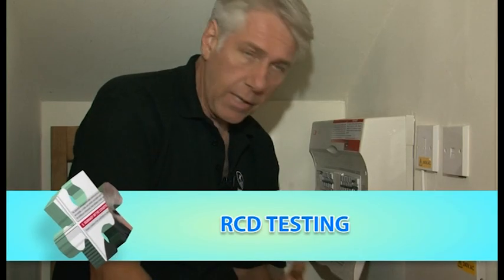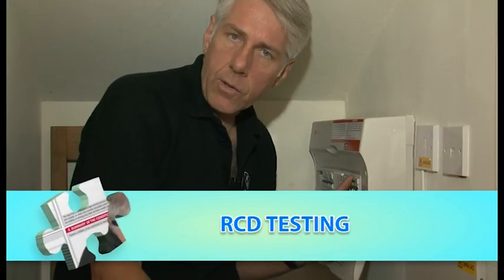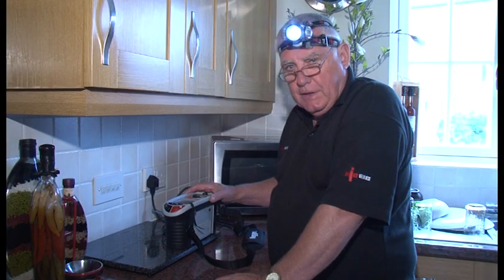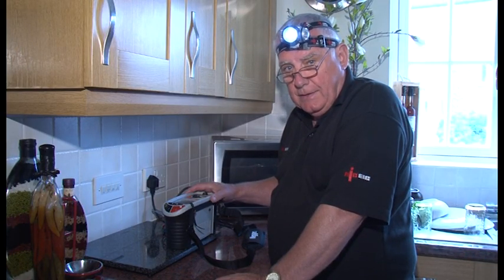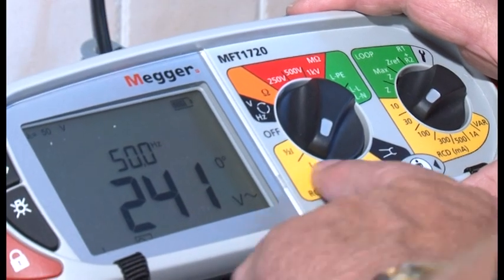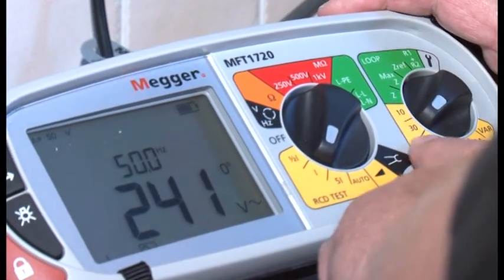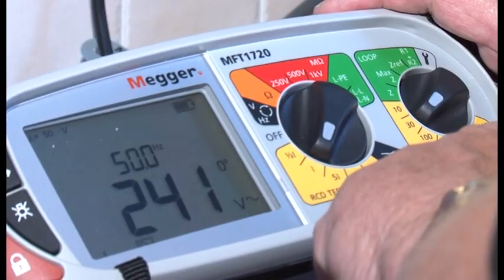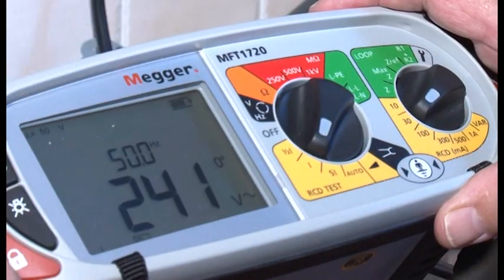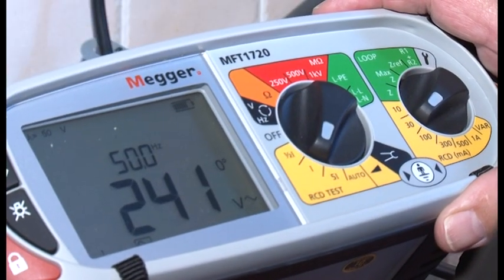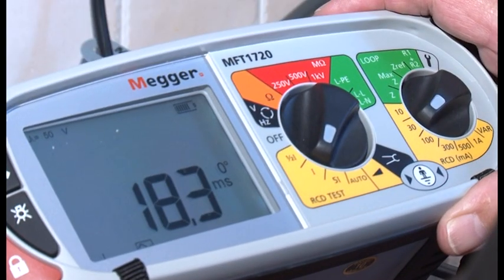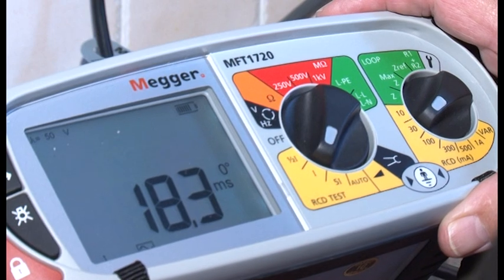As this installation has an RCD, we now need to check that its operation complies with the regs. For the first test, the RCD should operate at the rated current within 200 milliseconds. As you can see, I've got this side set on ×1. This side is set on 30 milliamps, which is the rating of the device. Now if I press the test button, and as you can see, we've got a reading of 18.3 milliseconds.